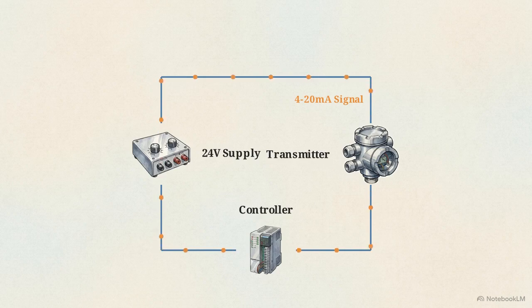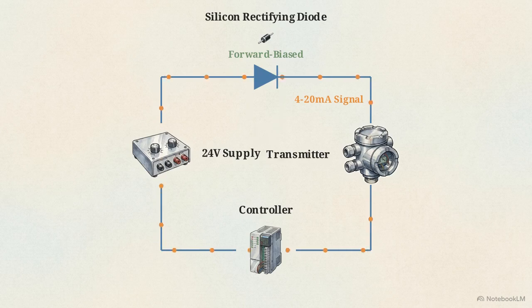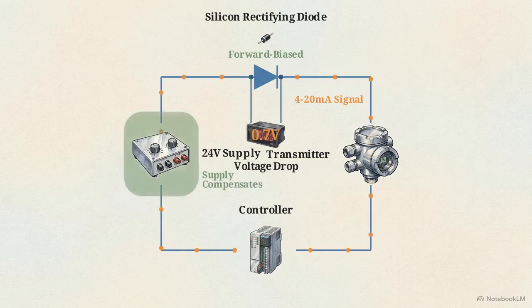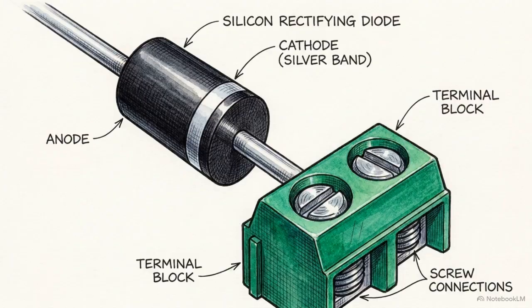A standard silicon rectifying diode is permanently installed directly in series with the transmitter loop. During normal operation, the signal simply flows through the forward bias diode. This adds a negligible voltage drop of about 0.7 volts, which the loop power supply easily overcomes. This simple piece of silicon creates a permanent diagnostic gateway.